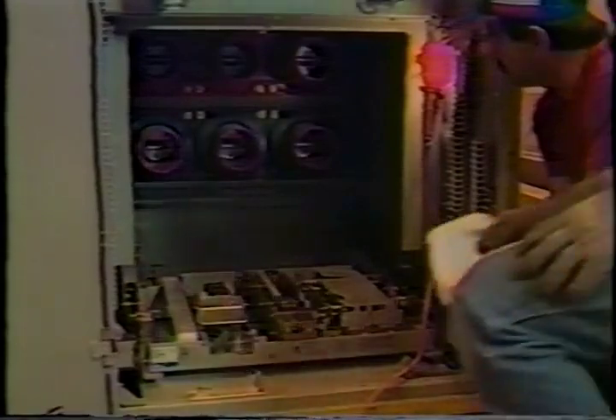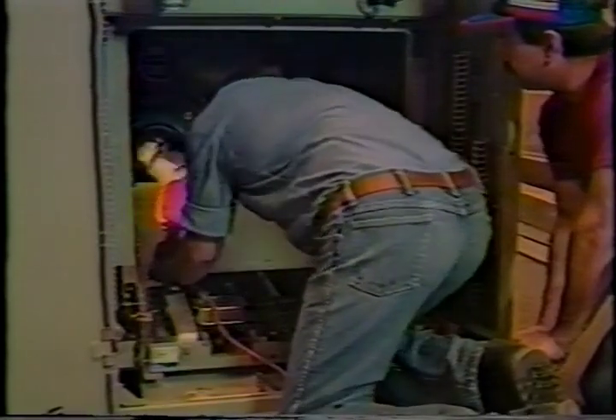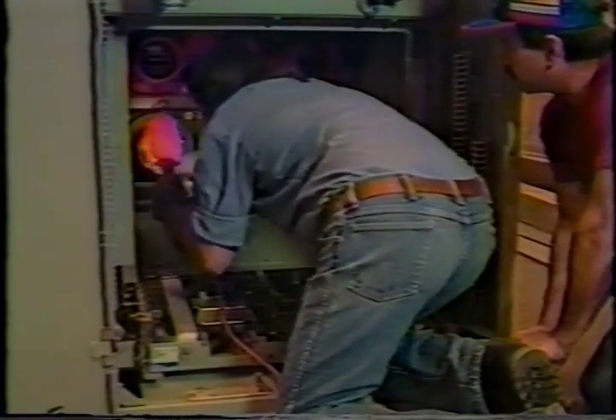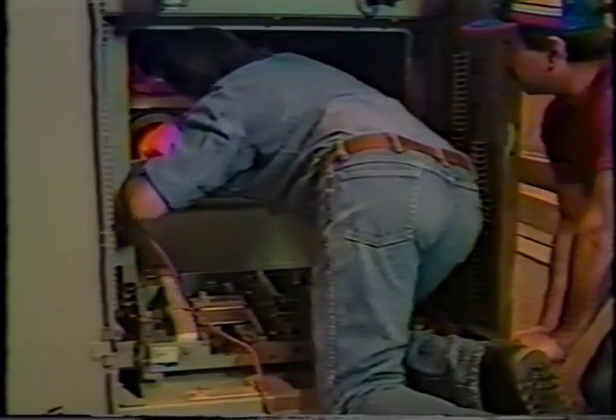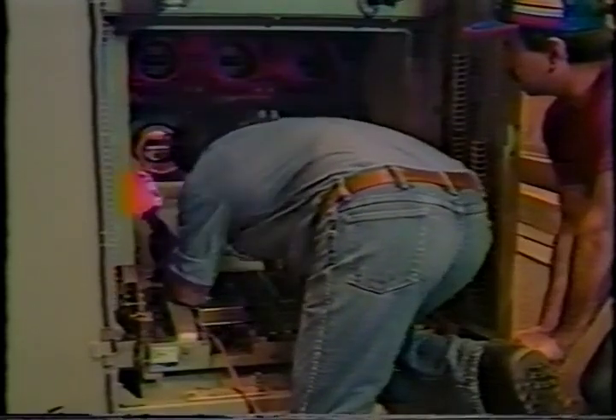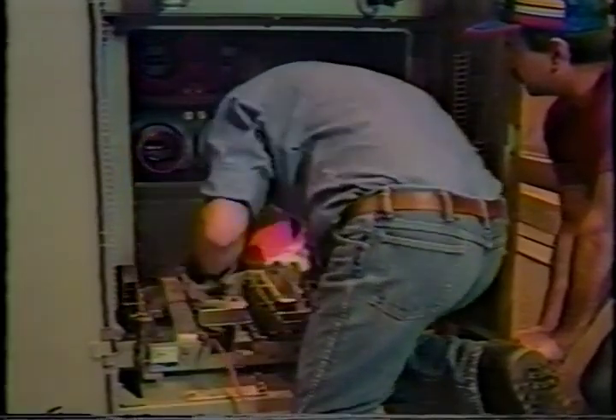When inspecting, repairing, and performing maintenance on metal-clad switchgear, the fact that dangerous voltages may exist must be kept in mind, and precautions must be taken to ensure that personnel do not come in contact with energized high-voltage parts. Failure to do so could result in personal injury or property damage. Some common general precautions for high voltage work are: all connections should be considered energized until the crew expecting to work on them is assured that the circuits are de-energized, and every possible precaution has been taken to see that there is no chance of a circuit being energized while the crew is working.